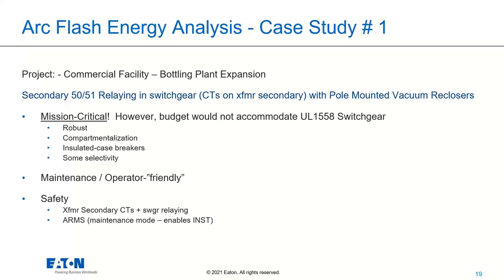So just looking at our first case study here, this was a bottling plant expansion. It was a heavy commercial facility where they're producing quite a bit of bottles of, in this case, a well-branded liquor, which keeps plenty of people happy. In this case, some of their mission critical requirements meant they were not able to accommodate arc resistant switchgear. They did want to have this robust nature of the equipment. They had some level of sensing capability. They were okay with adding in sensing and relaying. But probably the biggest one that came out of this is that they needed something that acted in an always on fashion.